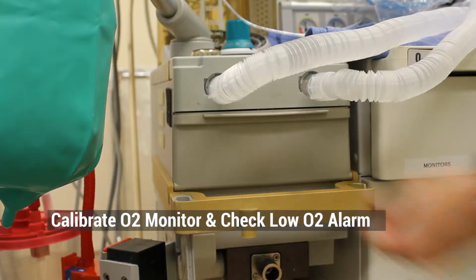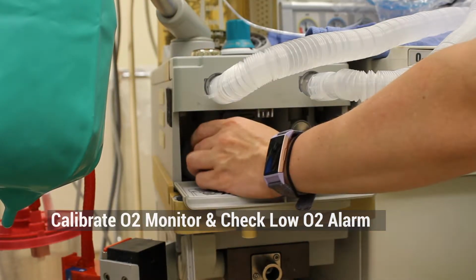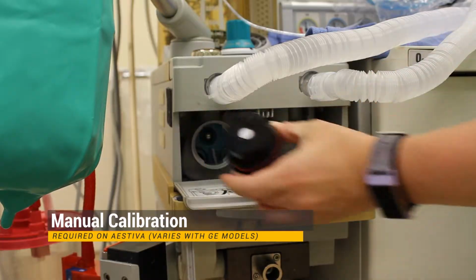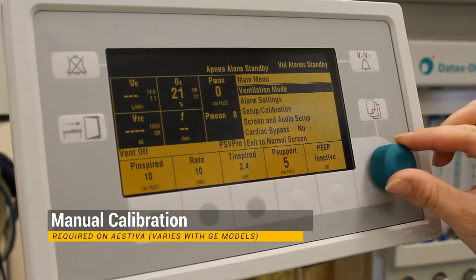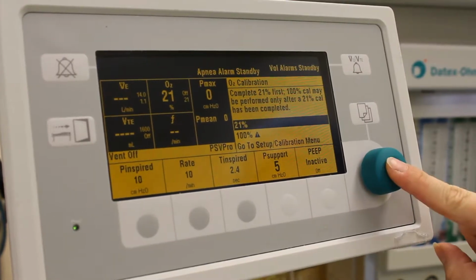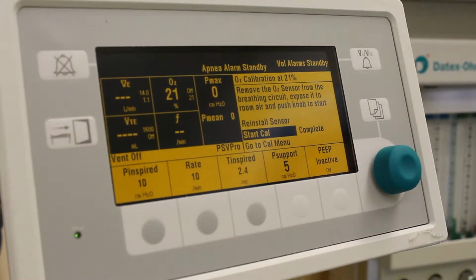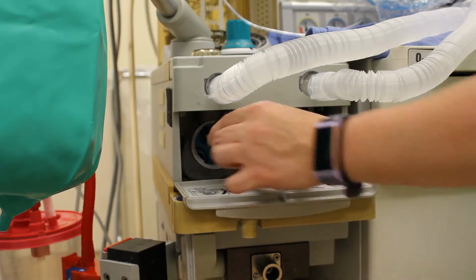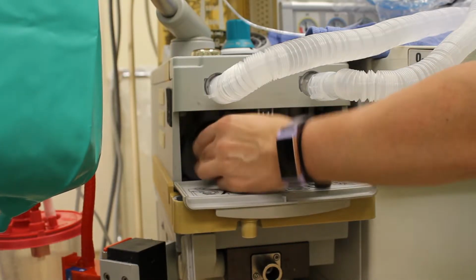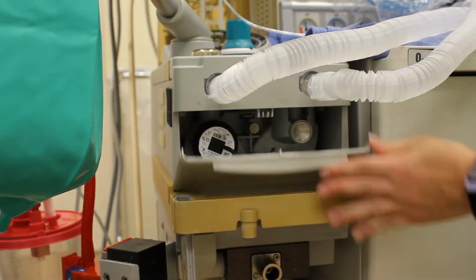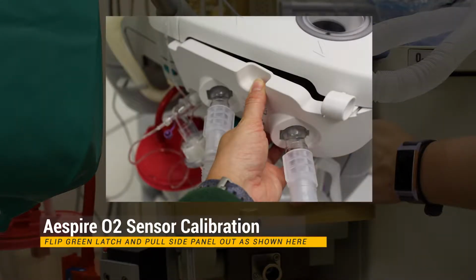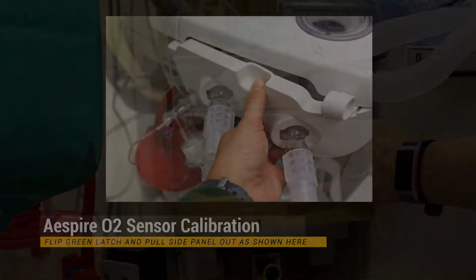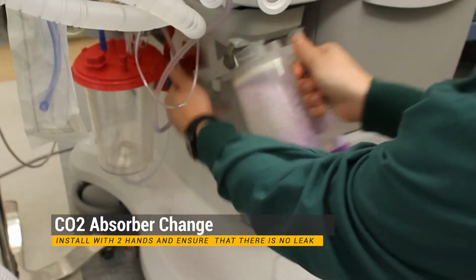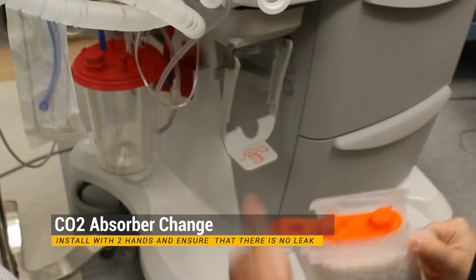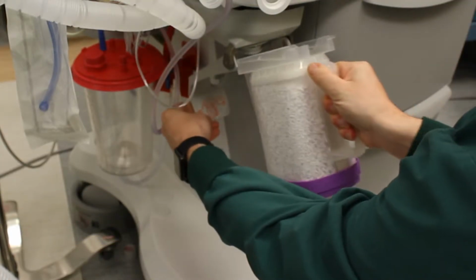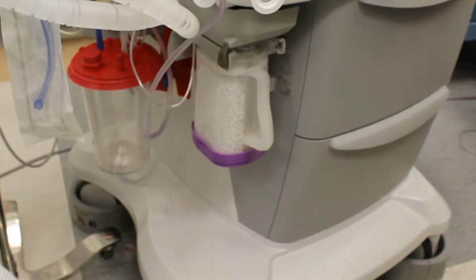Calibrate the oxygen monitor and check the low oxygen alarm. Check the status of the CO2 absorber and replace if necessary, as shown here. Always check that the absorber has no cracks and perform a pressure test after changing.